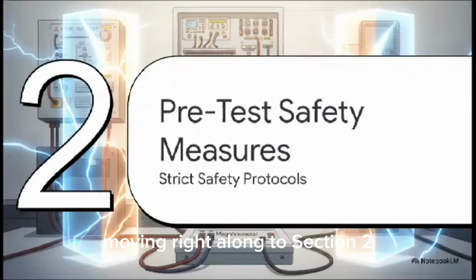Now you might be wondering, hey, why not just use my standard multimeter to check the wires? Well, a standard multimeter uses a very low voltage to measure low resistance. It's kind of like gently pouring water down a pipe to see if it's clear. But a megohmmeter applies high DC voltage. We're talking anywhere from 250 volts all the way up to a massive 5,000 volts. This massive electrical pressure actively pushes current through the system to expose those hidden high-resistance weaknesses that a normal everyday multimeter would completely miss. Moving right along to Section 2, crucial pre-test safety measures.